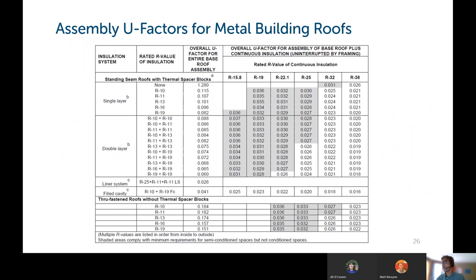This is a table located within the code, which shows different assemblies that you can do to meet the code requirements. Up at the top here, you've got the continuous R value of insulation that you're putting on top of the roof. You've got different ways of doing things on the left, like a single layer, double layer, liner system. And I will note that the gray areas are for the semi-conditioned spaces. Anything in gray should meet the semi-conditioned requirements. And then anything that is white will meet the standard code requirements. So if you're looking to do something that's not listed in the general R value requirements, you can use this table to find different ways of meeting the code, which is very helpful.